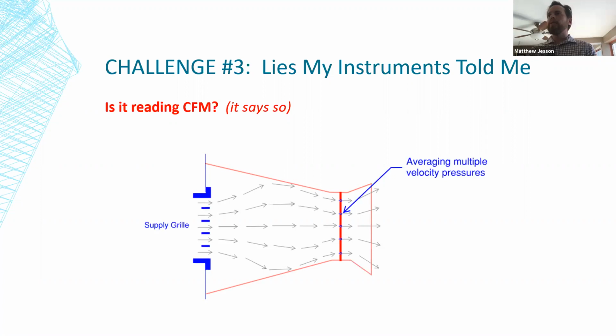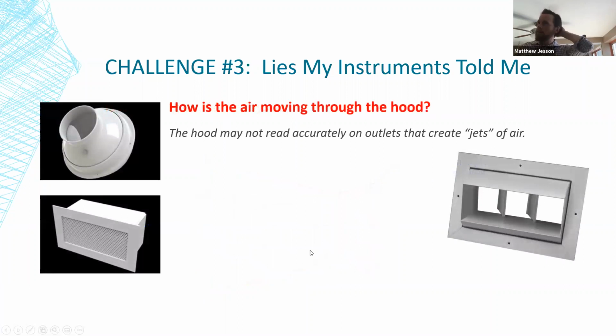As we were talking about earlier with this diagram, air comes through the diffuser, spreads out, hits the sides of the hood, washes against those sides, and comes down through what is usually a bell grid. But what that's doing is averaging multiple velocity pressures back to our square root of the sum rather than the sum of the square roots. It's a little less accurate depending on how even this velocity profile is. So it's really important to know that the hood might not read accurately, especially on outlets that have high throw that create jets of air, like those eyeball type nozzle diffusers, security grills, drum louvers.